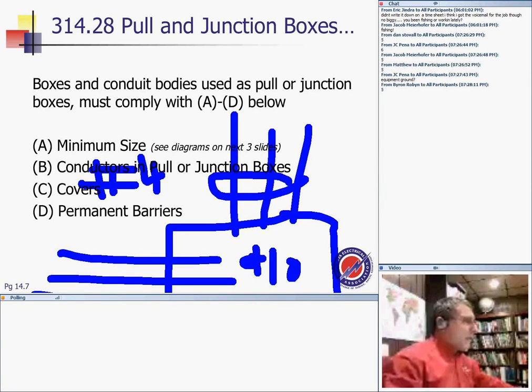For example, I have a box here and I bring multiple conductors here. These are 3 conductors, number 10, for example. And here, multiple conductors. All these conductors are number 4. And let's put a conduit around them just to make it legit. Here's my conduit around them, and my conduit on these. Now, this is not a J box. This is a pull box. Why is it a pull box? Because it has at least one conductor number 4 or more. Number 4 or more.